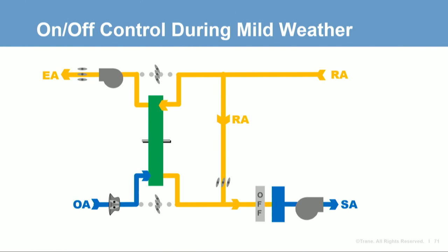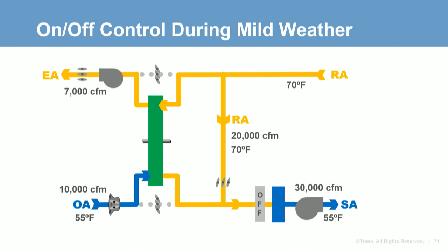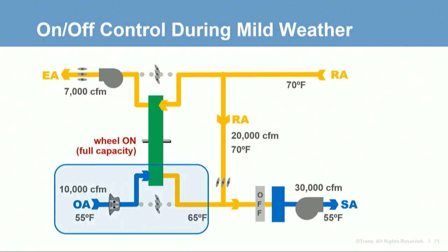To demonstrate, this schematic depicts an example mixed-air VAV system delivering 30,000 CFM of air at 55 degrees, using a wheel to exchange energy between 10,000 CFM of outdoor air and 7,000 CFM of exhaust. At a mild outdoor condition of 55 degrees, if the energy recovery device continues operating, it will transfer heat from the warmer 70-degree exhaust air to the cooler outdoor air, warming it to about 65 degrees. This preheated outdoor air mixes with recirculated return air for a mixed air temperature of 68 degrees, requiring the cooling coil to cool the air 13 degrees down to the 55-degree set point.